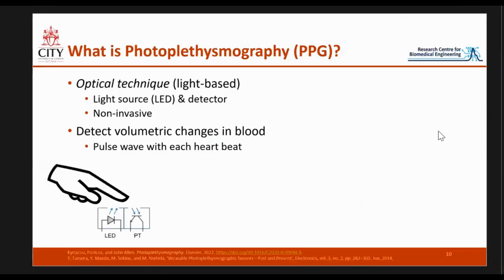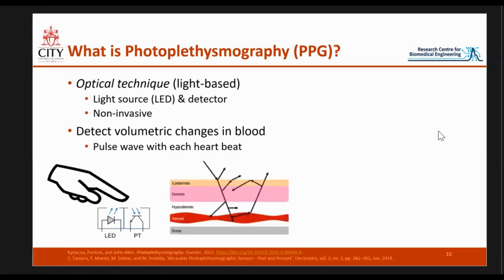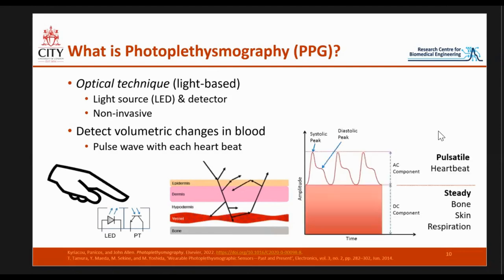Photoplethysmography is a light-based technique. It simply consists of a light source, like an LED, and a detector, making it completely non-invasive, and is able to detect volumetric changes in blood. By shining light into an area — for example, the finger or the ear — you detect the reflected light back. With each beat of the heart, it sends a pulse wave of expansion and contraction. When the blood vessel expands, the amount of light absorbed changes, and that absorbed light is detected by the photodetector, changing corresponding to the heartbeat to produce a PPG signal.